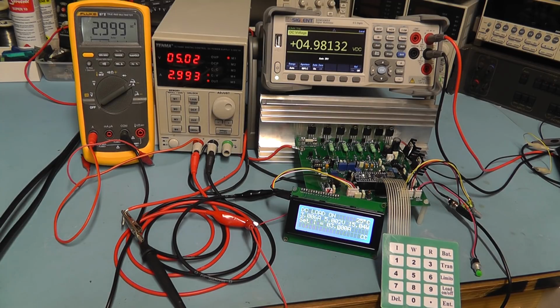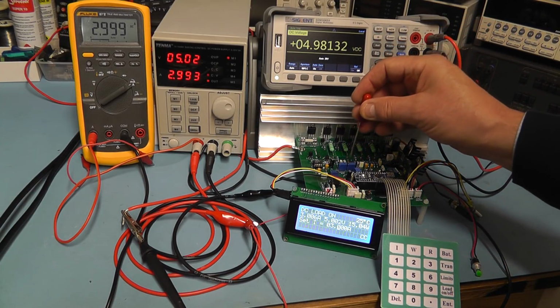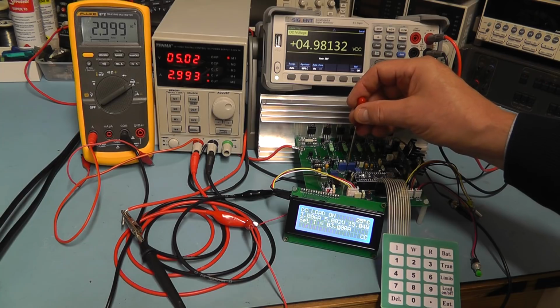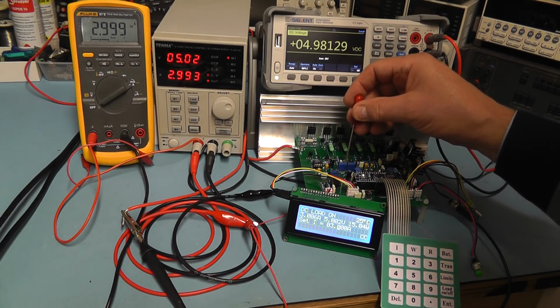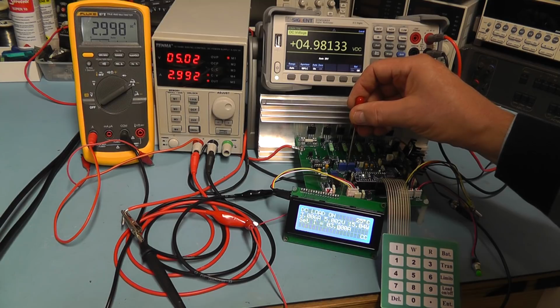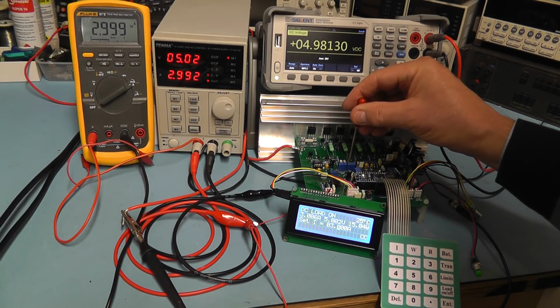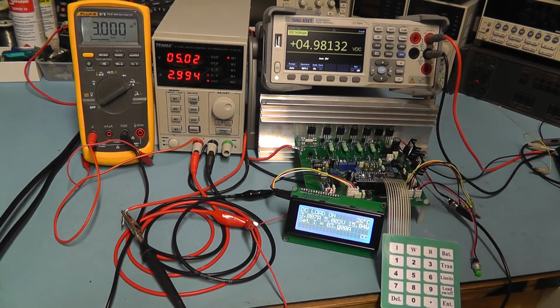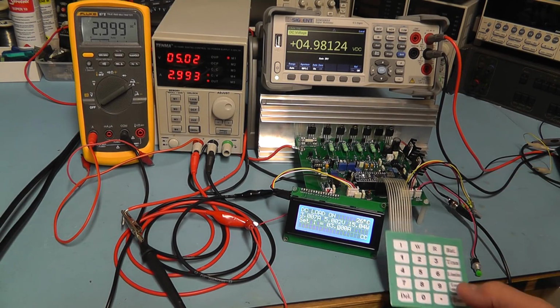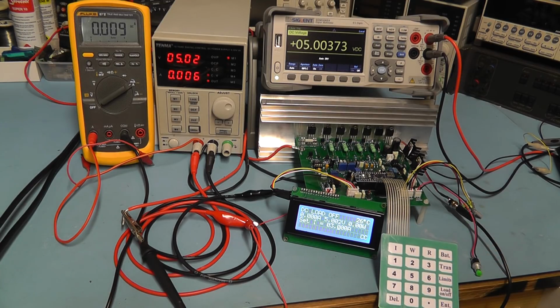It's showing us 2.999 on the Fluke. You can maybe just trim the current calibration preset one last time, just to increase it slightly. There we go. So that should be okay now. I will provide you with the details of calibration. It's a case of going backwards and forwards a few times with those two presets on a high current setting and then a low current setting. But I'll give you that detail as a download you can download and do yourself.